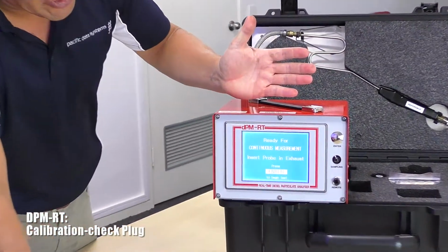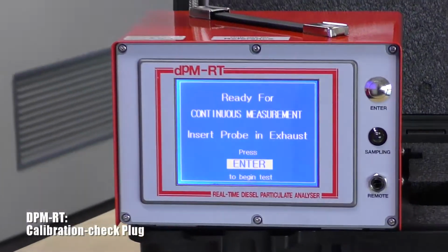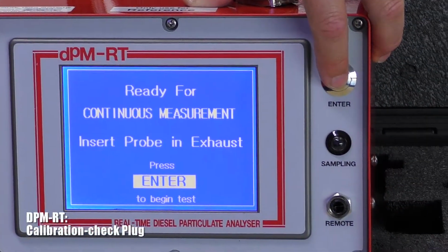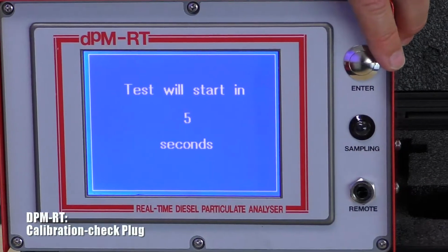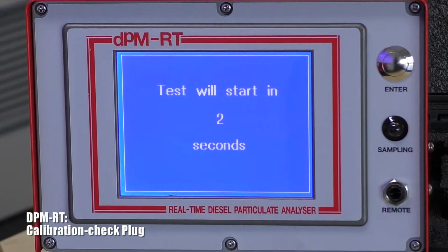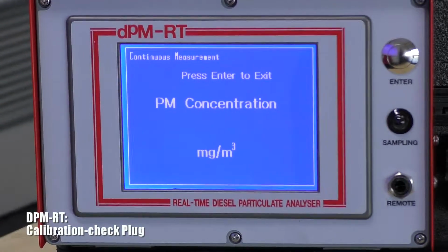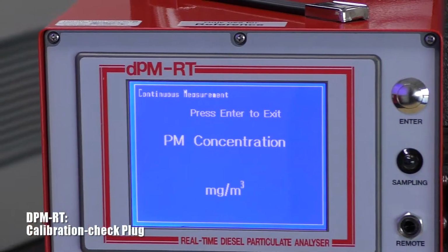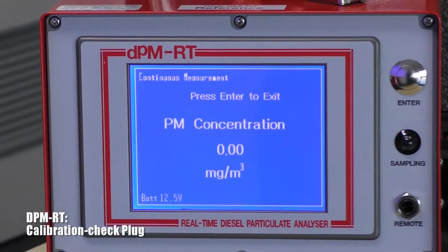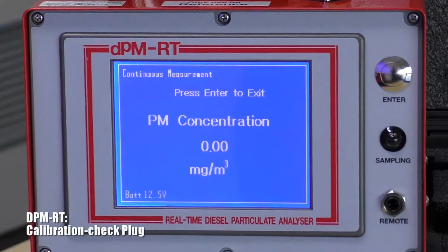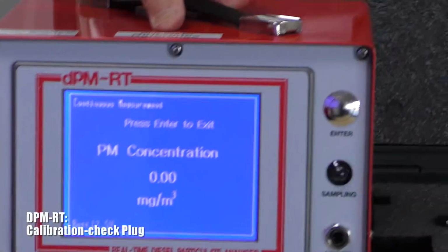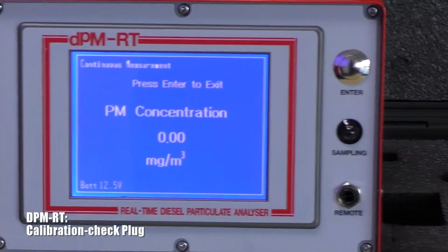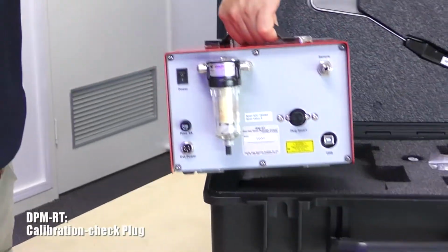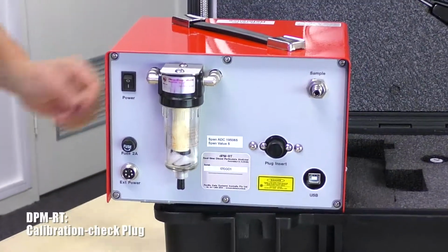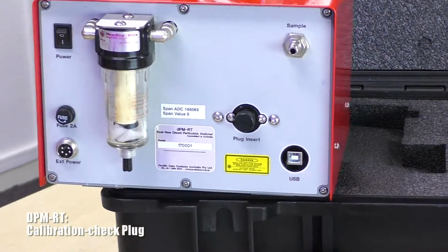The instrument has gone through its zero procedure and now it's ready for continuous measurement. You can select the enter button. The test will begin after the 5-second countdown ceases. The instrument is now in continuous mode, and you can see it is in clean air as 0.00 milligrams per cubic metre is displayed. You then, whilst the instrument is still running, turn the instrument around. You grab your calibration check plug ready.